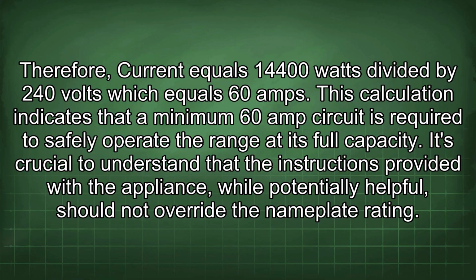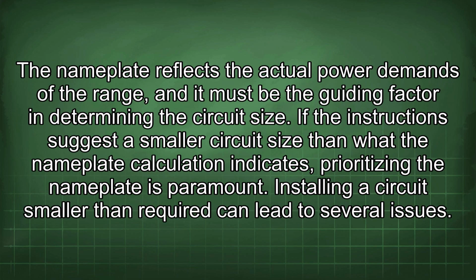It's crucial to understand that the instructions provided with the appliance, while potentially helpful, should not override the nameplate rating. The nameplate reflects the actual power demands of the range, and it must be the guiding factor in determining the circuit size. If the instructions suggest a smaller circuit size than what the nameplate calculation indicates, prioritizing the nameplate is paramount. Installing a circuit smaller than required can lead to several issues.